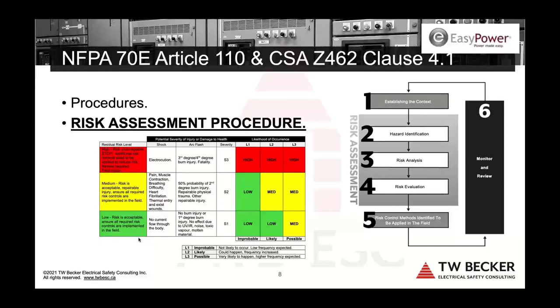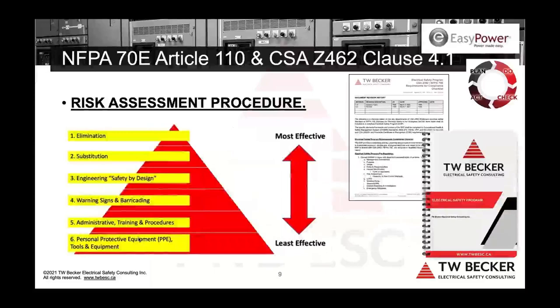This risk assessment procedure, the outcome is the hierarchy of risk control methods that you see in this graphic, top down. And we need top down risk control methods, not bottom up. The employer should not be buying arc flash PPE first and sending the workers on training and getting the studies and labels installed. It should be talking about how can we eliminate exposure, and yes, ultimately doing the risk assessment procedure to identify the appropriate PPE, to identify training as a need. You can see it's in the controls as item 5.